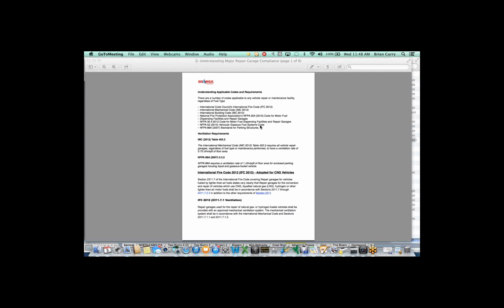Specifically, if you look at the ventilation requirement, we see this a lot with our shops. We've got 11 shops, and I ran a couple with 7 other shops. Any shop being built, especially the older ones, a lot of them were retrofits out of an existing building, which may have been a warehouse at one point, or never really built to be a vehicle repair shop, or it may be a brand new shop. Typically, and Steve and Ted touched upon this, in a vehicle repair shop per code, you pull the exhaust air down close to the ground, I believe 42 inches off the ground. You're typically not pulling it from the ceiling.